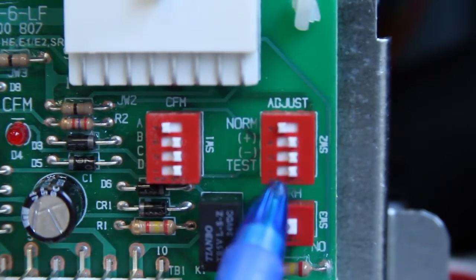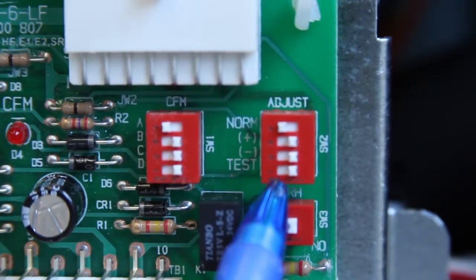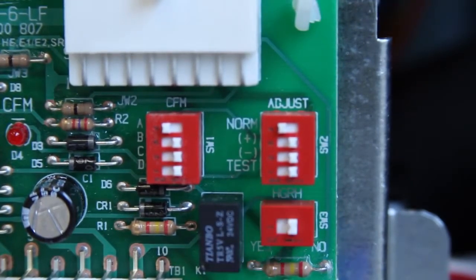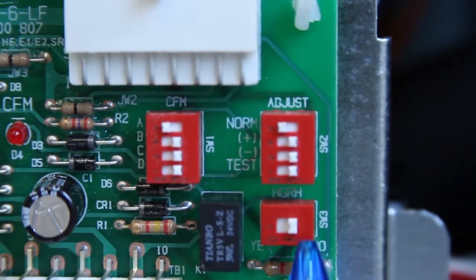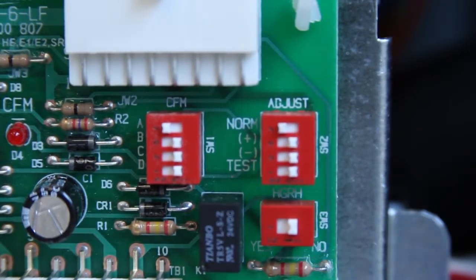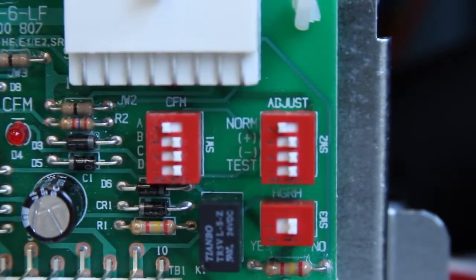There is also a test dip switch when placed in the on position and given a fan call from the thermostat, the motor should ramp up to 100% of the CFM. Just below those dip switches is one additional dip switch for hot gas reheat. There are 2 different types of dehumidification, one which is passive, which we talked about a little bit earlier, so that you can operate with this variable speed motor when you have a humidity enabled control.